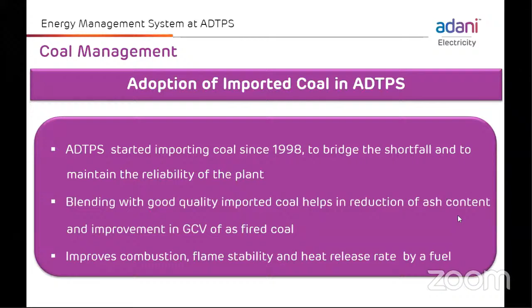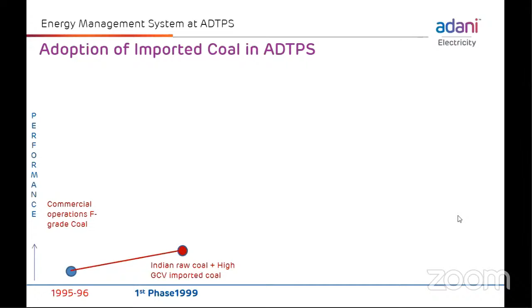In 1995, we started our commercial operation with F-grade Indian coal from SECL, Southeastern Coalfields Limited. Over the period, in the first phase in 1999, we started blending high GCV imported coal from Indonesia with the Indian raw coal. Because of this initiative, there is a reduction in coal quantity, emission, clinkering in the boiler, and auxiliary power consumption. And there is improvement in unit load, flame stability inside the boiler, and ultimately improvement in overall performance.